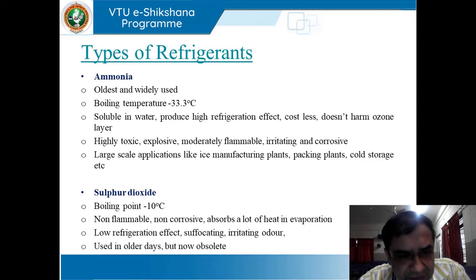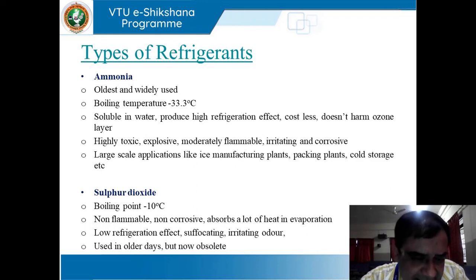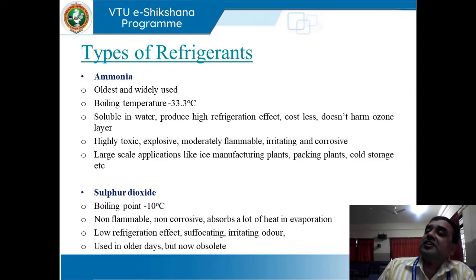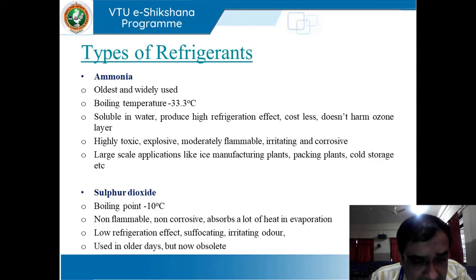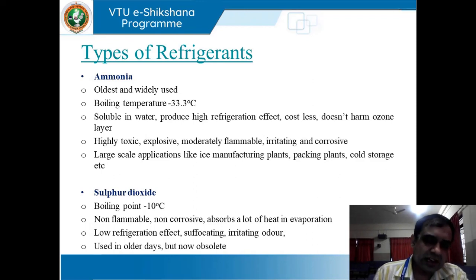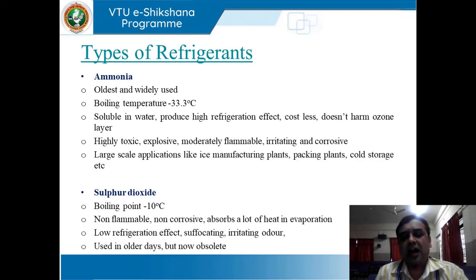When we come to types of refrigerants, we have ammonia — the oldest and most widely used. Its boiling point temperature is minus 33.3 degrees centigrade. It is soluble in water, produces a high refrigeration effect, is costless, and does not harm the ozone layer — which is very important. However, it is highly toxic, explosive, moderately flammable, irritating, and corrosive. It is used for large-scale applications like ice manufacturing plants, packing plants, and cold storage.